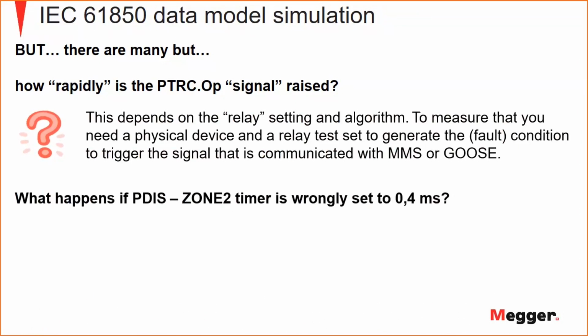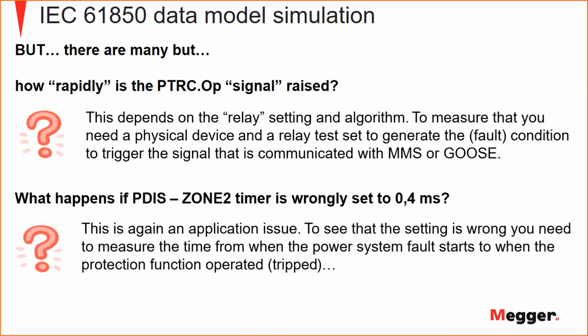Exactly. What happens if the PDIS distance protection function ZONE2 timer is wrongly set? Instead of setting it to 0.4 seconds, which normally we do, I set it to 0.4 milliseconds because I didn't read that the unit is in milliseconds. And this happens. You will not be able to see this with the data model simulation. It is again an application issue, and the setting is wrong. To see that the setting is wrong, you need to measure the time from when the power system fault happens to when the protection function operates or trips.